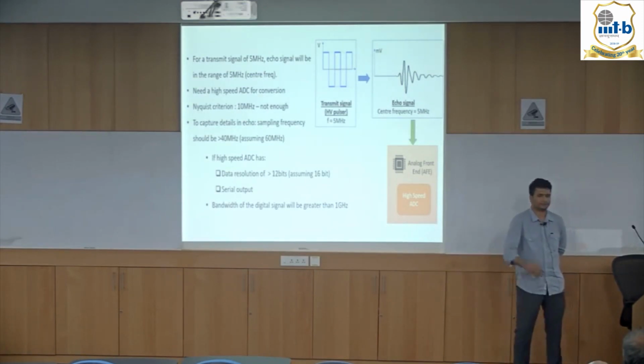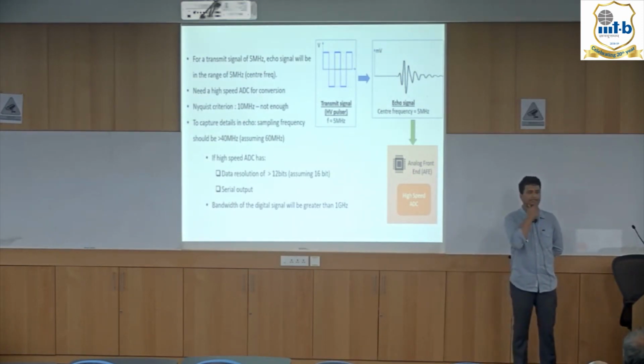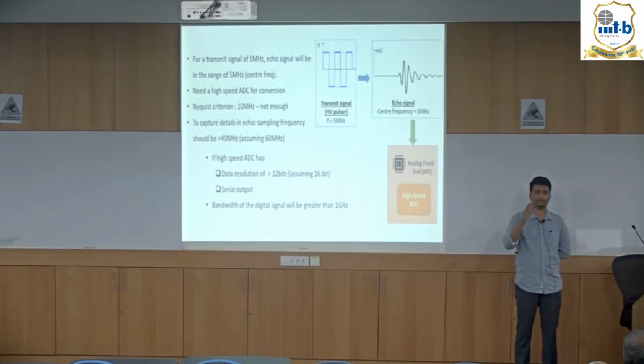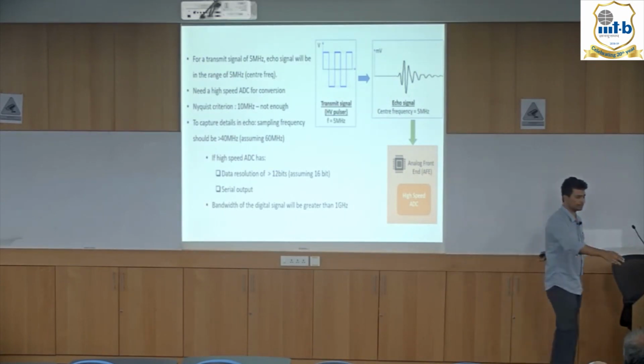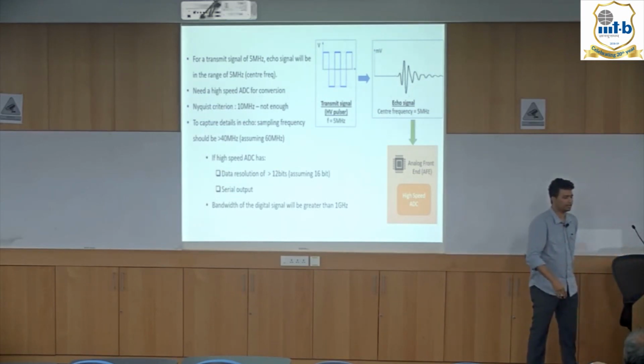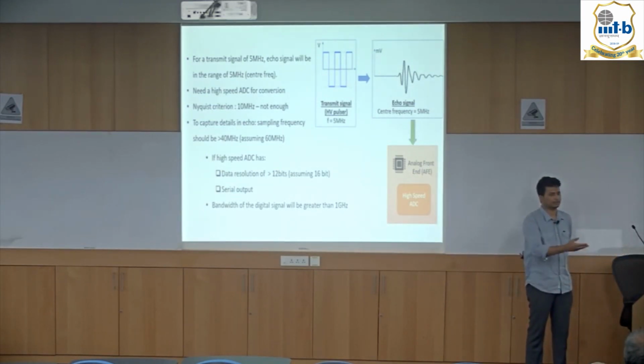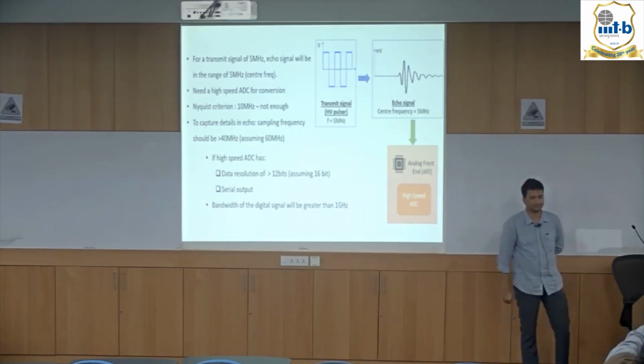So for example, if we trigger the ultrasound transducer using a 5 megahertz electric pulse, the echo will also have a center frequency of 5 megahertz. You can see we are giving a square pulse, but it is an attenuated sine pulse or a Gaussian attenuated pulse, so its frequency response varies.